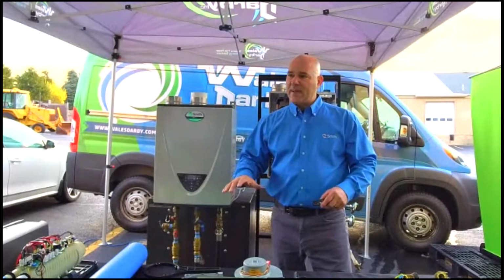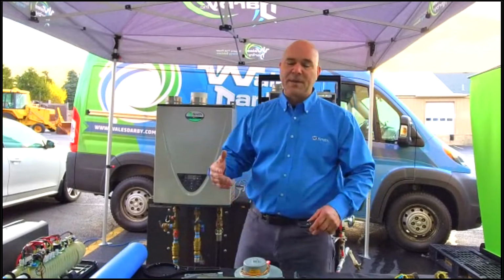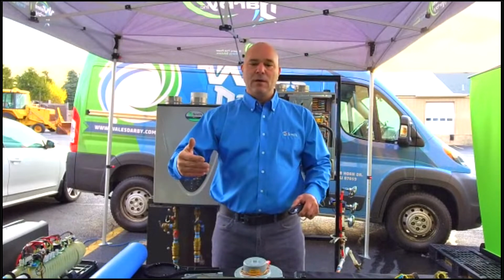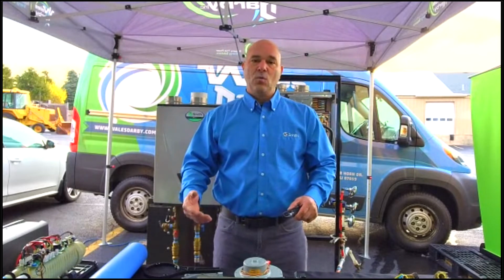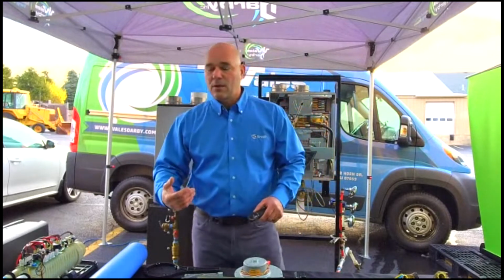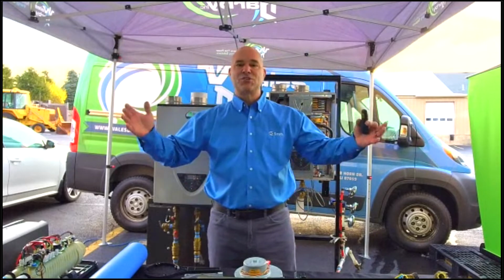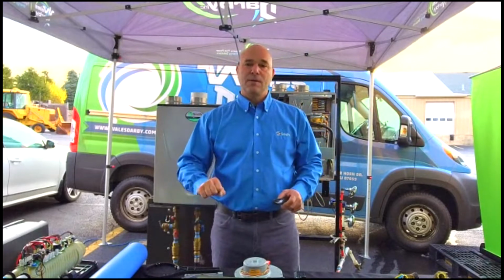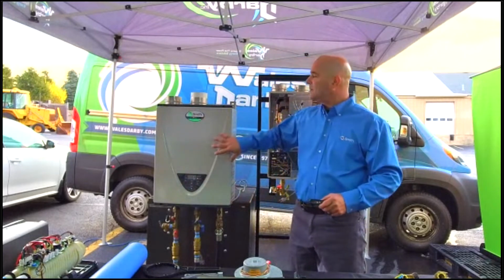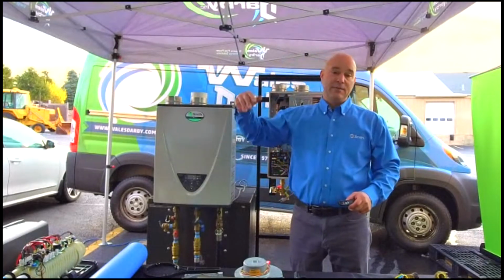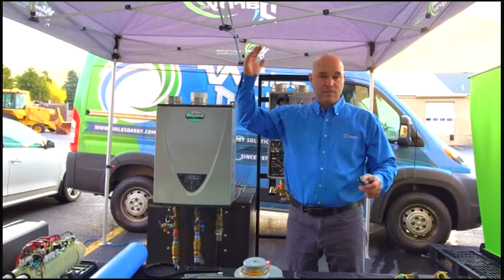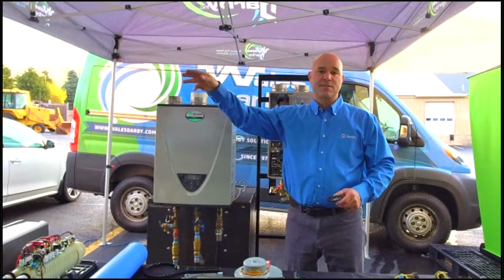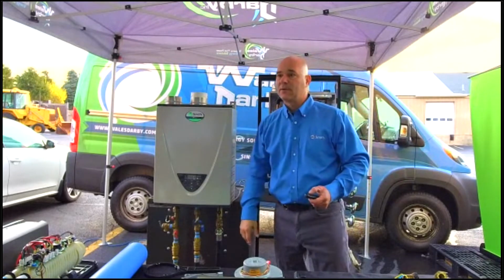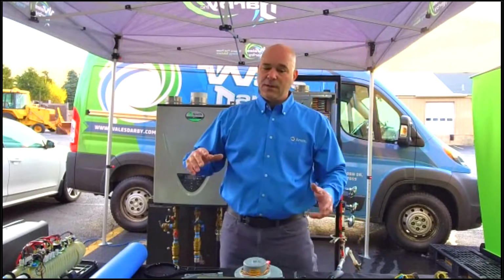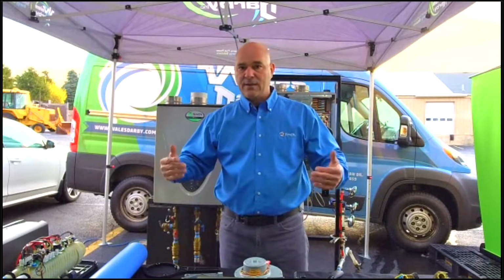So if you're out there speccing tankless, it's always important to know what am I up against, right? What do I have to do to support the demands and expectations of the homeowner? So we need to understand the temperature of the water coming in. And in our region, we can be anywhere from 37 to 51-ish degrees in our footprint for groundwater. So we need to know that when we're speccing out a tankless unit, whether it's electric or gas, because we have to have the ability to elevate that temperature, leaving the ground, coming into our home, elevate it to call it 120 degrees, and then deliver it to the appliances within the home, showers, washers, dishwashers, whatever. So our area, this New Jersey, New York, Lower Hudson Valley area, that's where we cover.